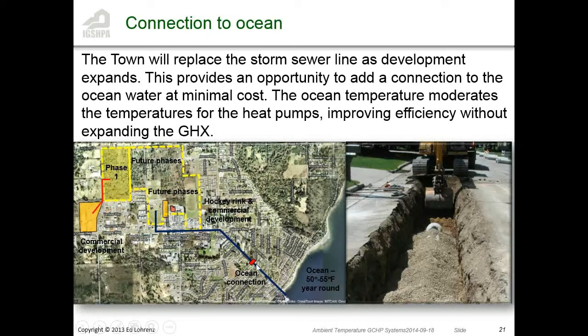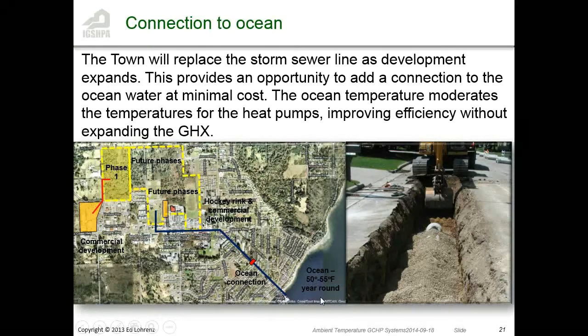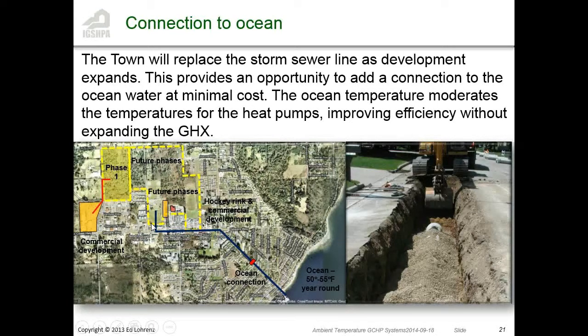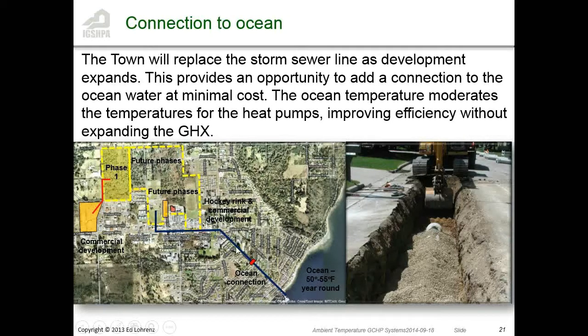Simply adding a heat exchanger at some point here, ocean water we knew was going to be about 50 to 55 degrees year-round, and we could use that to moderate the temperature of the ground. When this gets completely built, if the buildings weren't quite what we expected, if it became heating dominant or cooling dominant, this could be the pressure relief valve. If it got too hot, this is a beautiful temperature to dump heat into. If it became too cold, we can still extract a fair bit of energy by running the fluid from the ground loop through a heat exchanger and running ocean water through the other side of it.